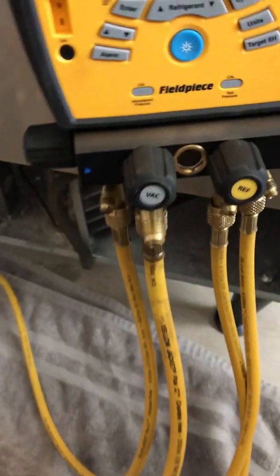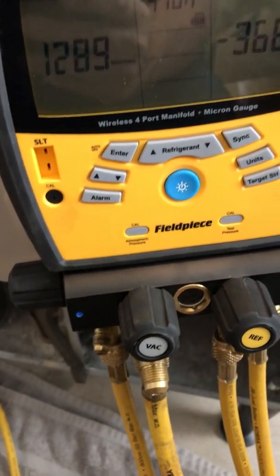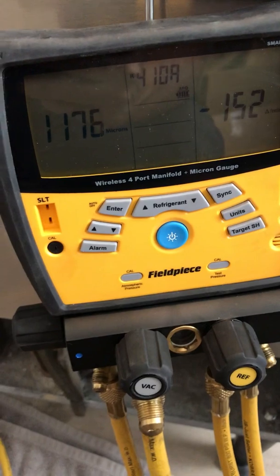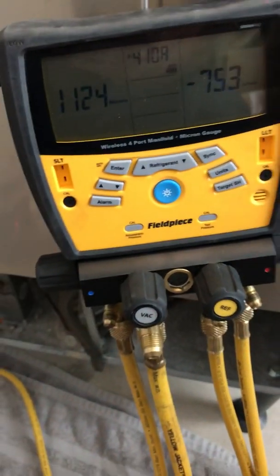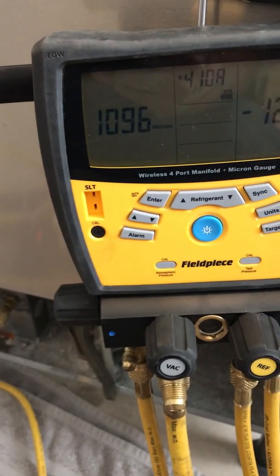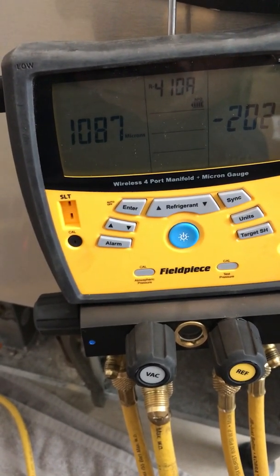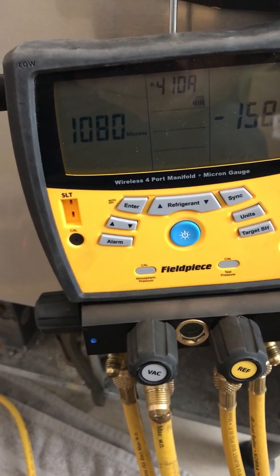Right now I'm just pulling out of the standard hoses — I don't have the larger hose on yet — but we're just watching it, we're hauling ass. You can really see how this cordless vacuum pump from NAVAC, the 4 CFM, really took off when it saw the pressure. It had like an idle mode, and as soon as you get the gauges on and you're pulling a vacuum, it cranks and does its thing.